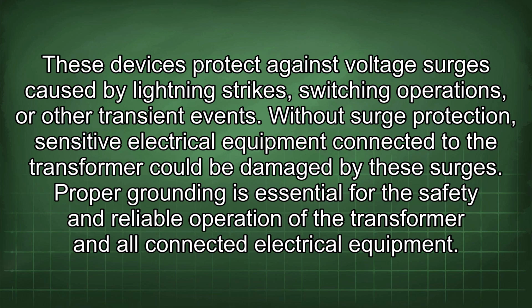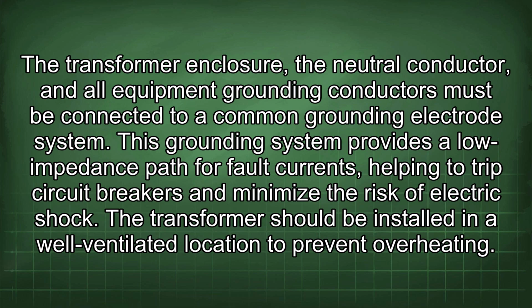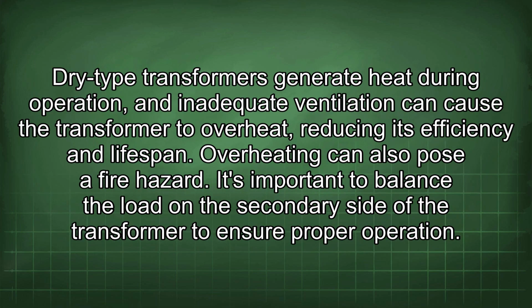Proper grounding is essential for the safety and reliable operation of the transformer and all connected electrical equipment. The transformer enclosure, the neutral conductor, and all equipment grounding conductors must be connected to a common grounding electrode system. This grounding system provides a low impedance path for fault currents, helping to trip circuit breakers and minimize the risk of electric shock. The transformer should be installed in a well-ventilated location to prevent overheating. Dry-type transformers generate heat during operation, and inadequate ventilation can cause the transformer to overheat, reducing its efficiency and lifespan. Overheating can also pose a fire hazard.